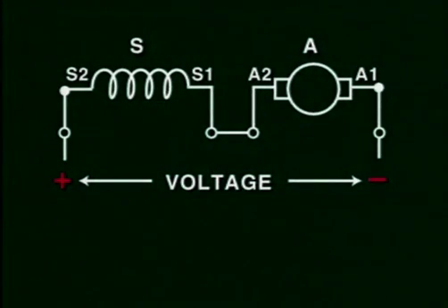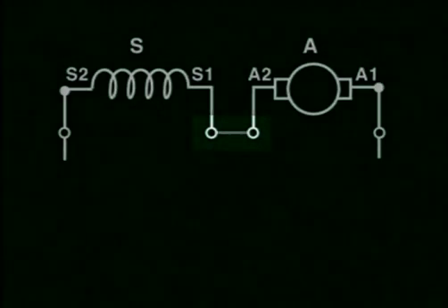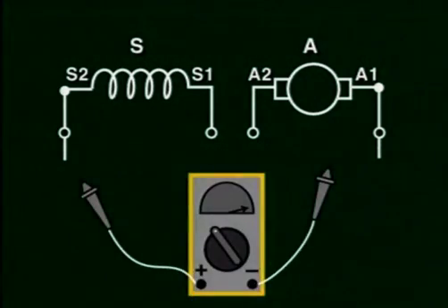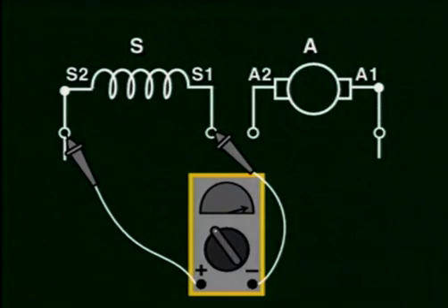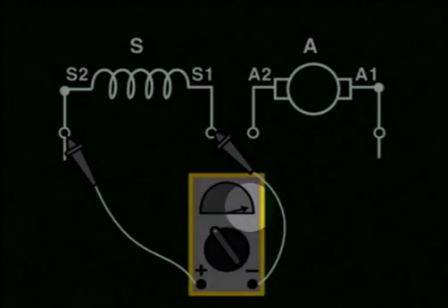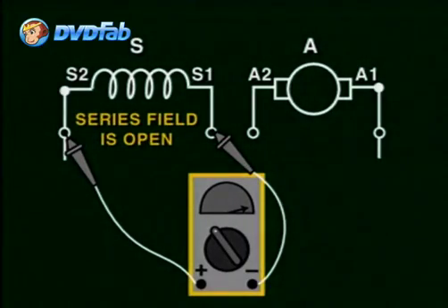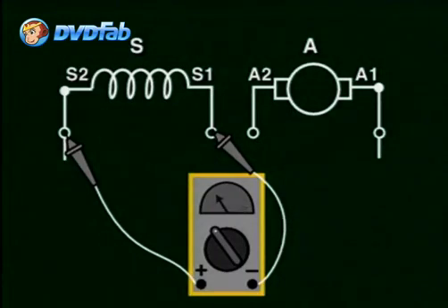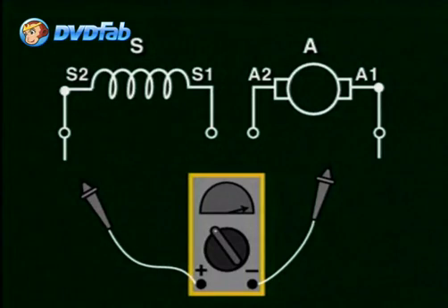To proceed, you should disconnect the power to the motor and disconnect the series field and armature to test for an open condition. By placing the meter with a selection for ohms to read resistance across the S1 and S2 terminals of the field, we could test to see if an open is present. If the ohm meter shows an infinity reading, then the series field is open, which means that it needs to be rewound or replaced. If the meter reads an ohms reading because there is resistance in the winding, then there is continuity and the series field winding is okay. Regardless of both readings, you should continue the test and inspect the armature, because even if the series field was open, there could still be another problem with the armature.